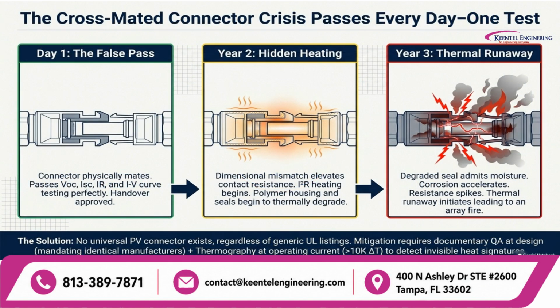Cross-mated connectors are among the leading root causes of utility-scale array fires, and they easily fool day one testing. On day one, cross-mated connectors from different manufacturers physically click together and pass continuity, VOC, and insulation tests flawlessly. By year 2, micromillimeter dimensional tolerances create elevated contact resistance, triggering I²R resistive heating and degrading the polymer housing. By year 3, thermal degradation admits moisture, corrosion accelerates exponentially, and an arcing fire occurs. The solution requires strict design QA, enforcing identical connector pairings and infrared thermography under full load.